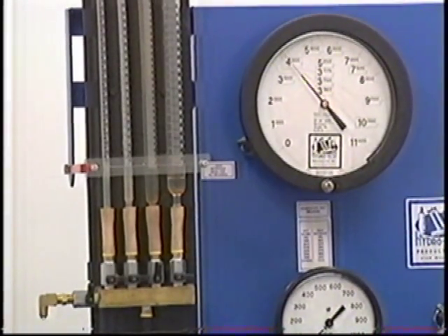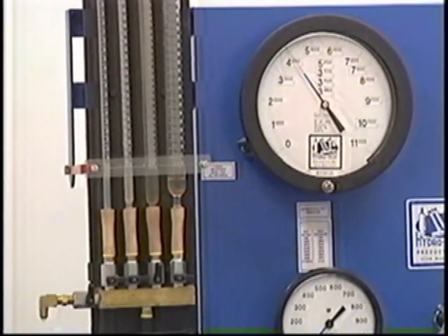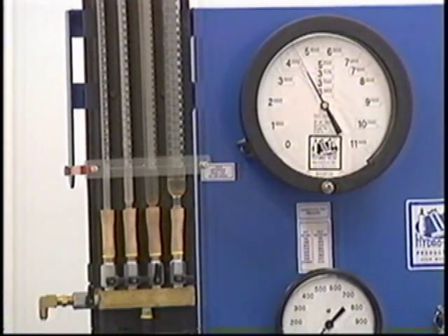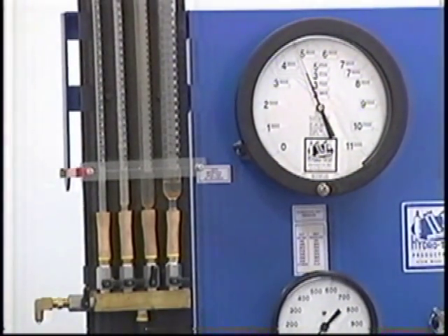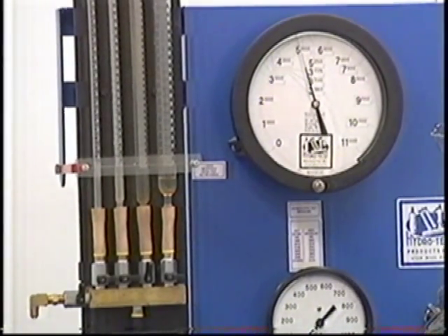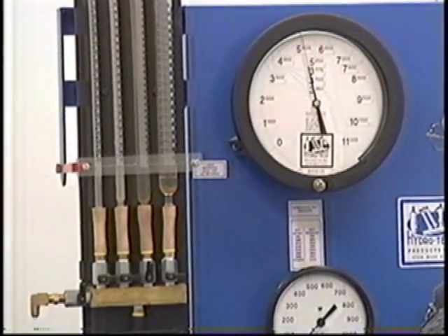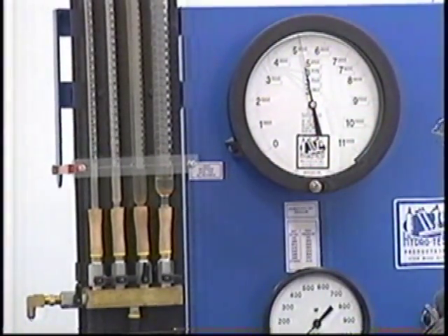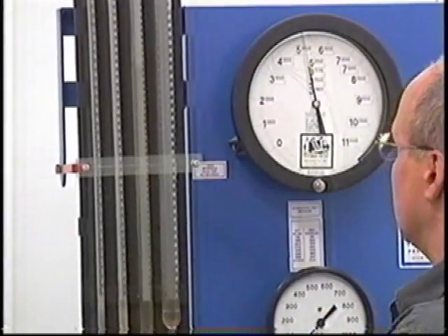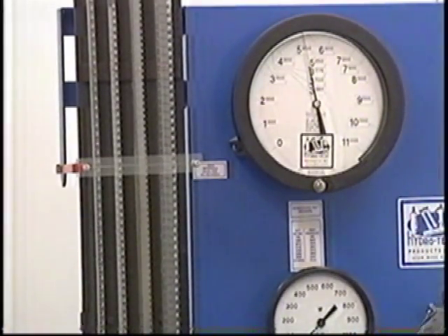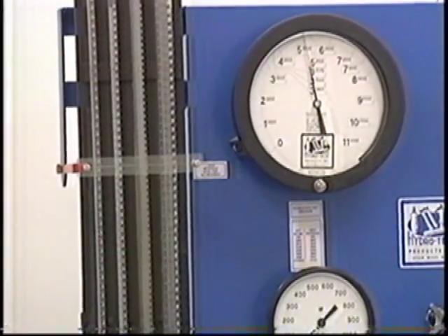I will then bring it all the way up to 5000 psi. Again tap the gauge. You are required to hold the pressure for 30 seconds, that is why we have a clock.